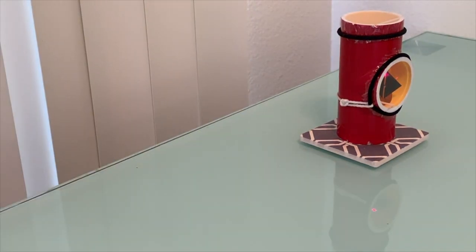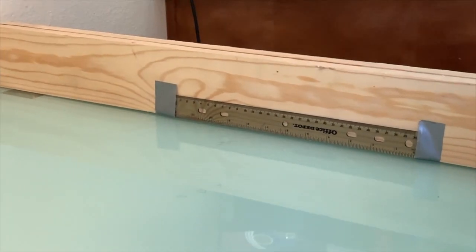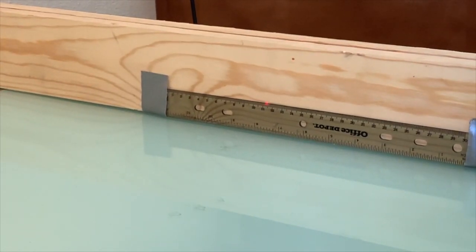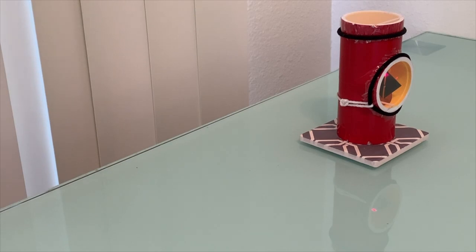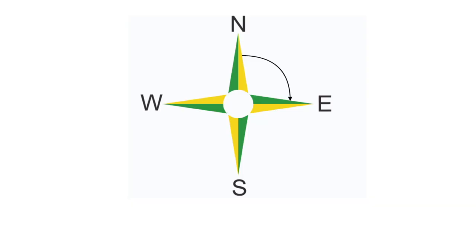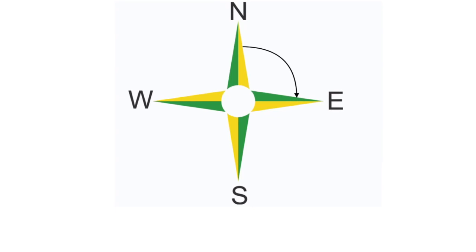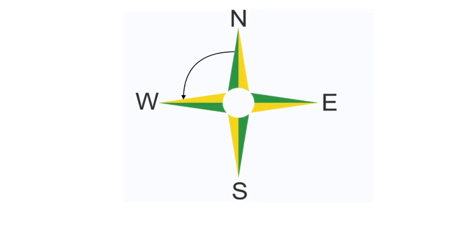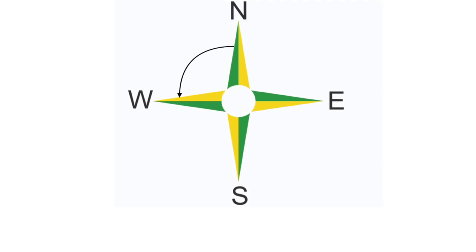Now, pick a place to set up your instrument. You'll want to mount the scale about 2 meters or 6 feet away from the sensor. And, you want to mount the sensor so that it's facing either magnetic east, that is, 90 degrees clockwise from magnetic north, or magnetic west, which is, of course, 90 degrees counterclockwise from magnetic north.